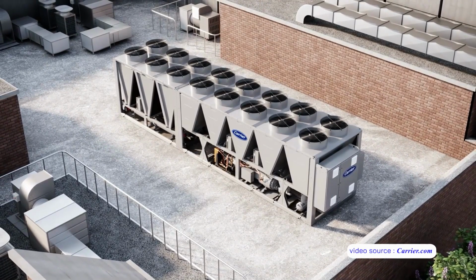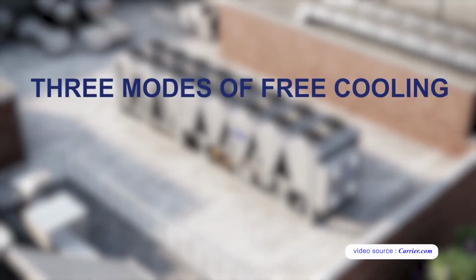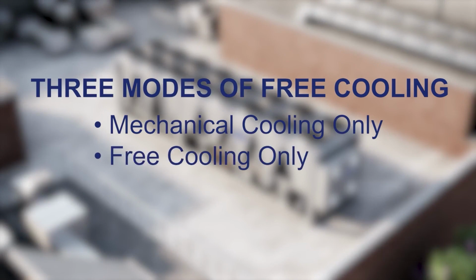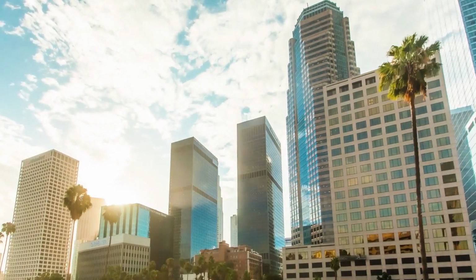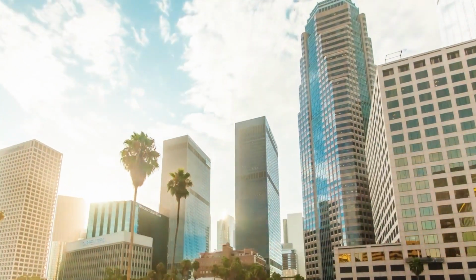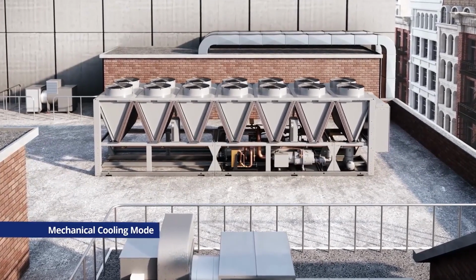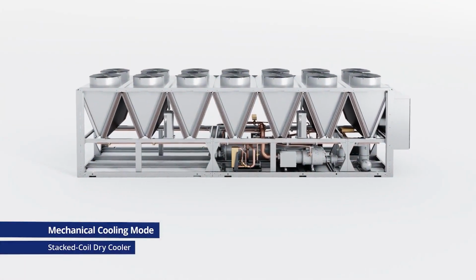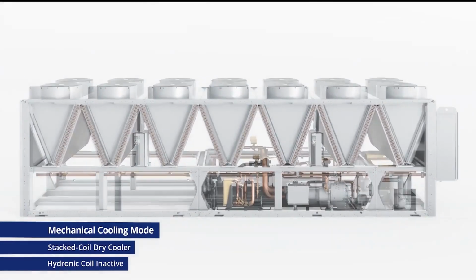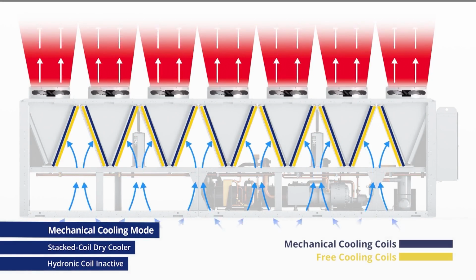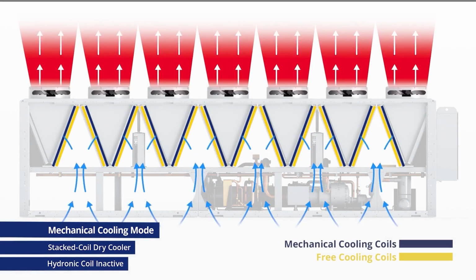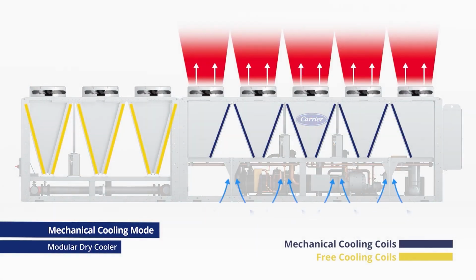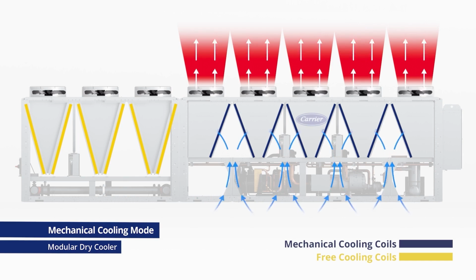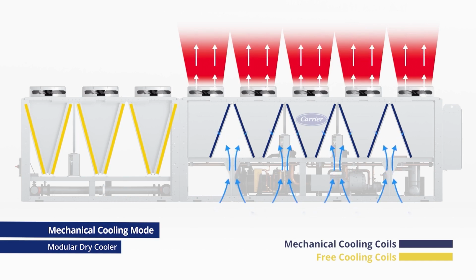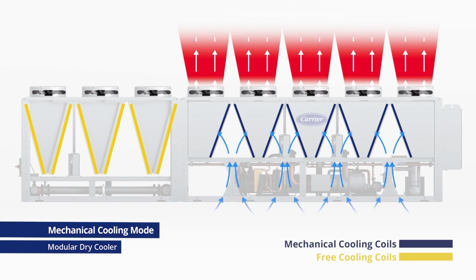Let's examine why. A free cooling system will run in one of three modes: mechanical cooling only, free cooling only, or a hybrid mode, where mechanical cooling and free cooling occur simultaneously. When the ambient temperature is too high to provide free cooling, the chiller operates in mechanical cooling only mode. In this case, the fans on the stacked coil design need to force air through both the chiller condenser coils and the unused free cooling coils, wasting energy. The modular design is different. When it's in mechanical cooling mode, the air flows only over the mechanical cooling coils that are in use, while the fans for free cooling are turned off, saving energy.